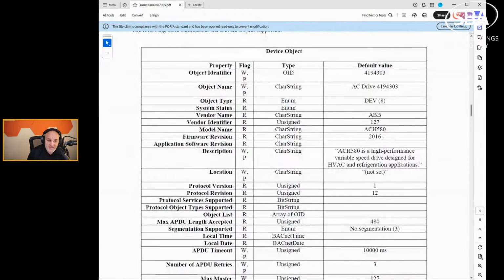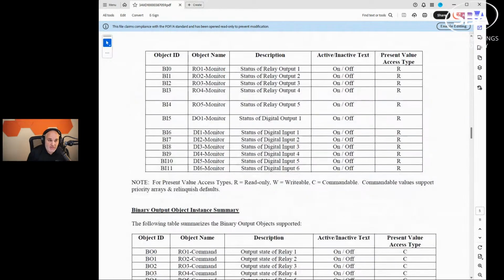Assuming baud rate and device ID are set up, and assuming your RS-485 standard wiring distance and node count is set up, then it is simply a matter at this point of going in and executing a Who-Is, which is quite simply a discovery of the device. So you should find the device, and when the device comes up, add it to your tree, and then do an I-Have object discovery, and you'll discover your sub objects and you'll map in all your points.